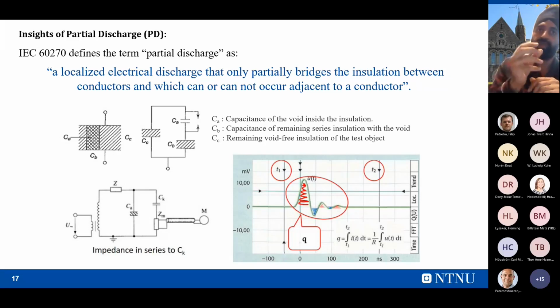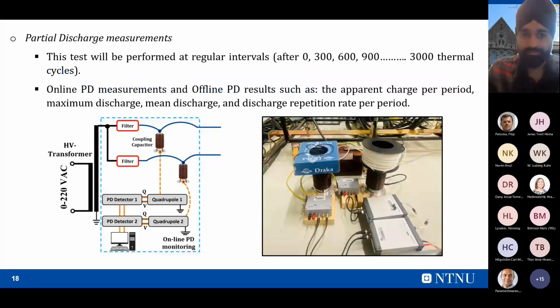Now based on that charge we try to find out what types of defects are present inside the insulation, whether it is because of a small void, a gap or delamination, or abrasion. For this we make some standards by artificially creating the defects and taking the data, so that for a given type of defect, if this kind of pattern appears, there might be a chance of this type of defect being present inside the insulation. So the setup for partial discharge is shown here.